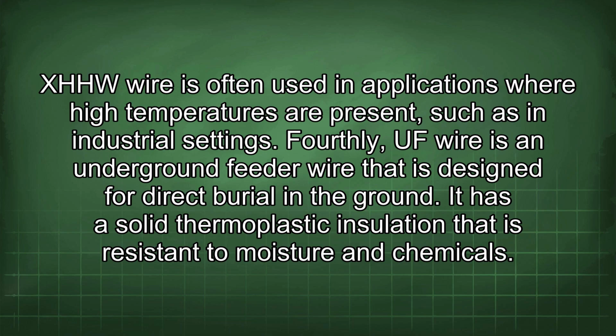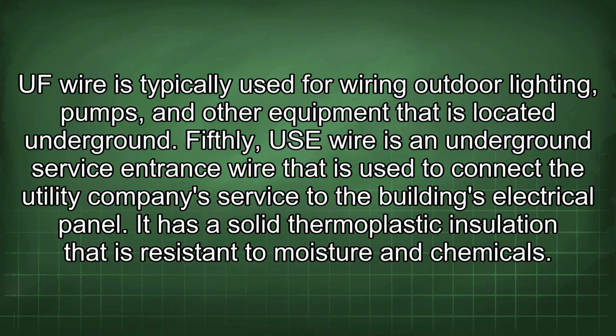Fourthly, UF wire is an underground feeder wire that is designed for direct burial in the ground. It has a solid thermoplastic insulation that is resistant to moisture and chemicals. UF wire is typically used for wiring outdoor lighting, pumps, and other equipment that is located underground.